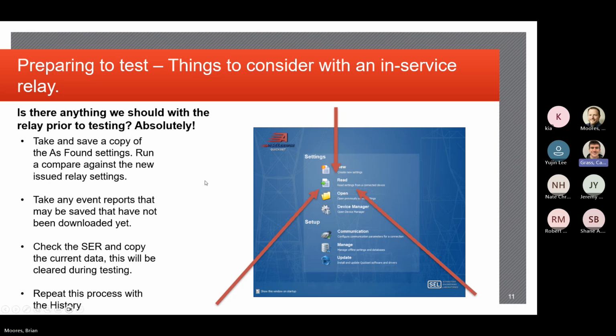Brian, one thing I want to add, if you don't mind. For the SER that he was just talking about, the sequential event recorder, that command is going to be used primarily during your relay testing. So if you can save a copy of whatever was in the relay prior to initiating your testing, that would be really good, just to provide to the client that this is what we found prior to doing any of our work. The SER is going to be utilized during your whole testing process to evaluate the outputs, trigger any of the inputs, and any of the protective relay elements that the relay is going to be initiating with the new settings that are going to be involved.